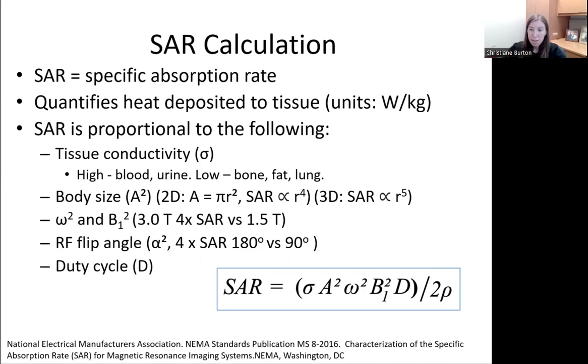This follows from the fact that the flip angle is proportional to the mean amplitude of the RF pulse, B1. Since SAR is proportional to B1 squared, it is also proportional to the square of the flip angle. So for example, a 180-degree pulse would create 4 times the SAR as a 90-degree pulse. SAR is proportional to the duty cycle, which represents the percent time in a pulse sequence that RF is being transmitted. A more intense sequence with lots of RF pulses applied in a short period of time will generate a high level of SAR.